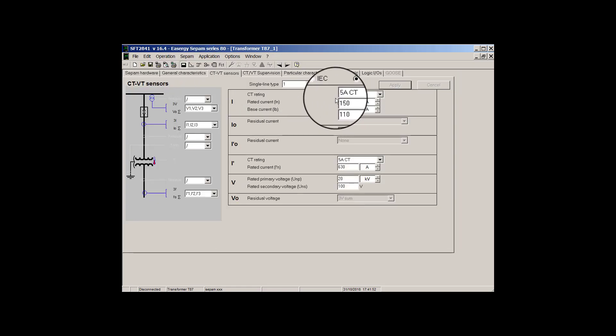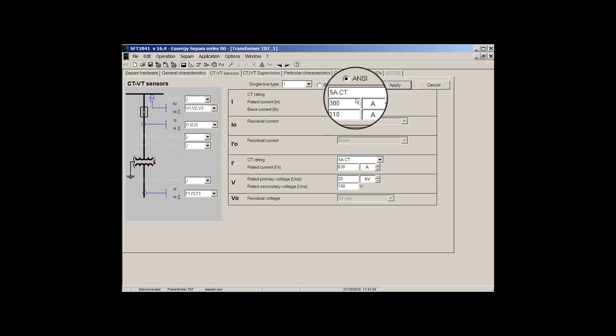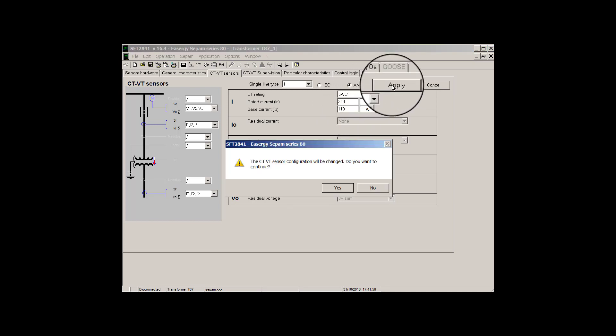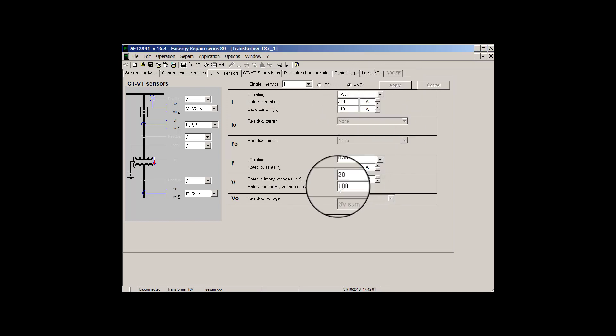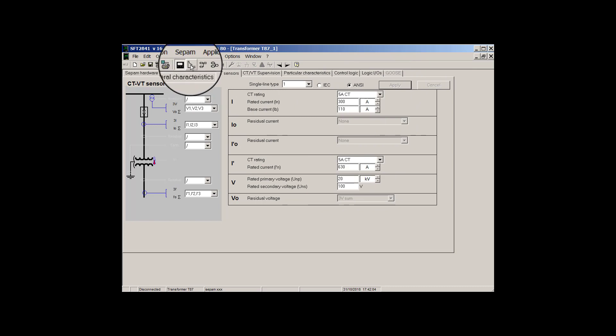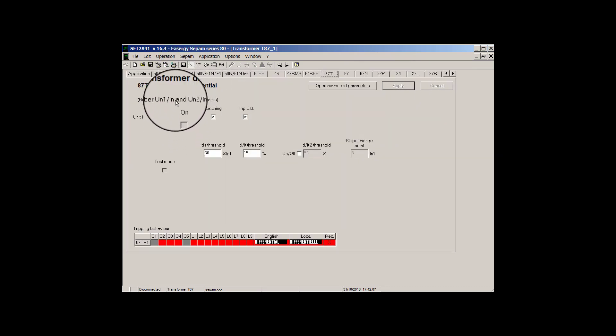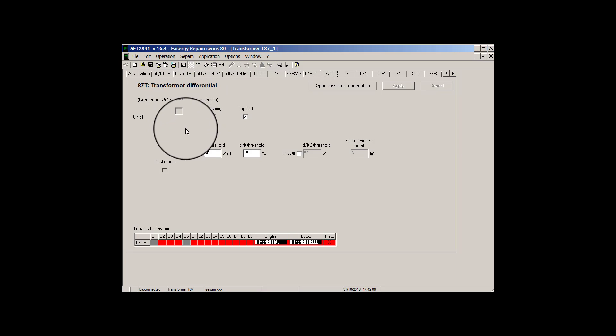But if we size CT out of range, so I will choose a number above 275, let's set it to 300. So for sure SFT will accept it, but again I check it in differential protection. As you see, we are not anymore allowed to enable differential protection.